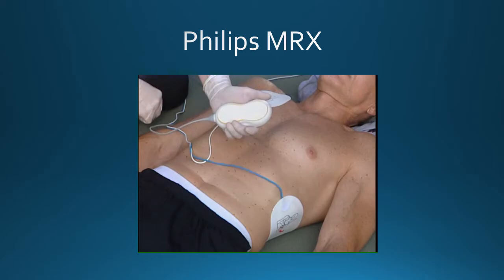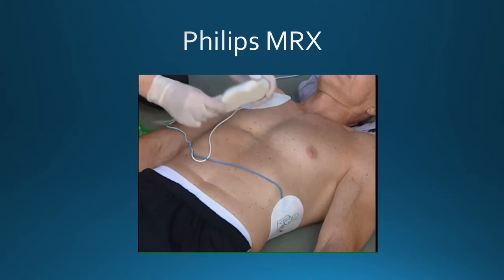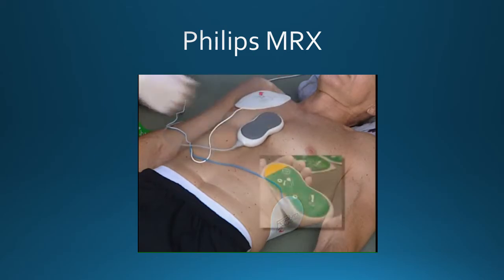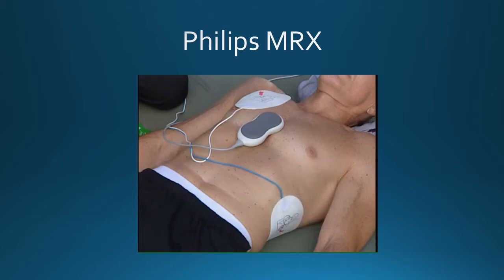the green liner away from the sensor adhesive pad. Position the compression sensor on the patient as shown in the graphic displayed on the green liner, which is on the lower half of the sternum. This is the same location where you would place the heel of your hand while performing CPR without the compression sensor.